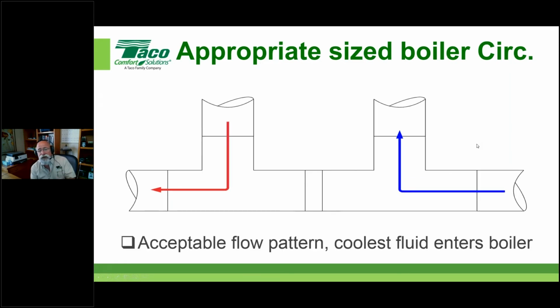Okay. Here's an acceptable flow pattern. People go, what do you mean by acceptable? That looks perfect to me. Yeah, but if I have a primary secondary piping configuration, I have a dead space right here. Why do I even have it, right? The other thing is people say, well, I've got two pumps on there. What if I just make the pumps the same size? Won't I get this as an end result? I'll say, well, it's really hard to do. It's acceptable, but just not very practical, right?